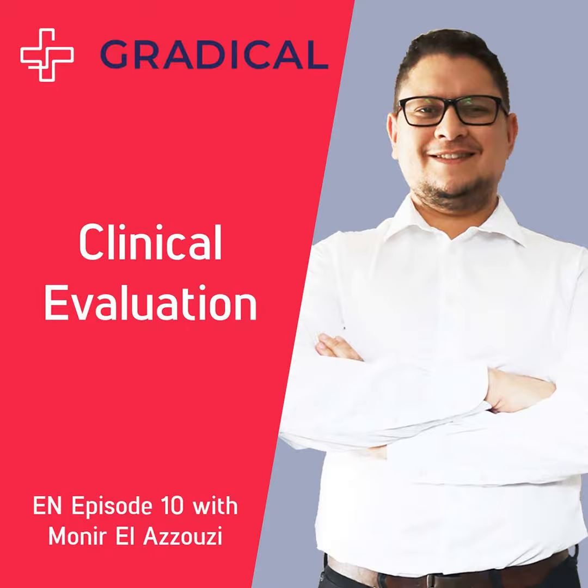a clinical investigation, which means that you maybe have to go through research on patients again. But this time you will not make the clinical investigation on the previous outcomes, because those were already clarified. You will just make a clinical investigation on the new outcomes and new functionalities of your device. And the point here is that you cannot really use your previous device as an equivalent if there are a lot of differences between them.